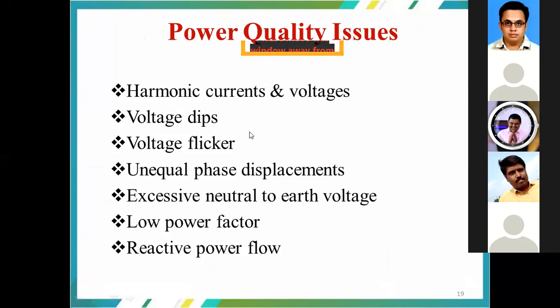So what are all the things we are going to consider as power quality issues? The harmonic currents and voltages, voltage dips due to various factors, unequal phase displacements, excessive neutral to earth voltage, low power factor, and the reactive power flow across the network.